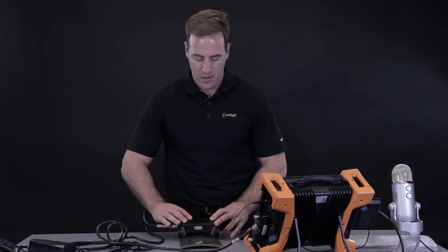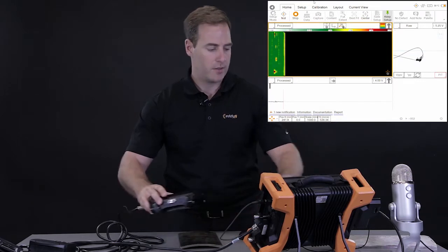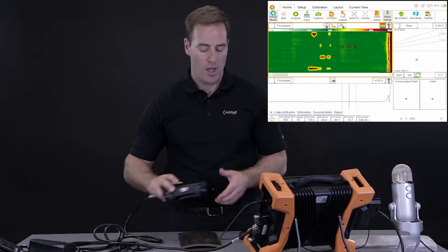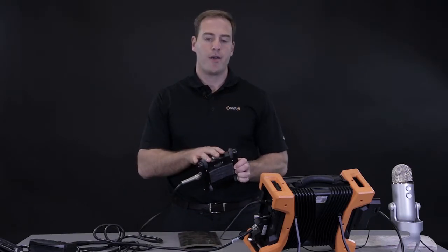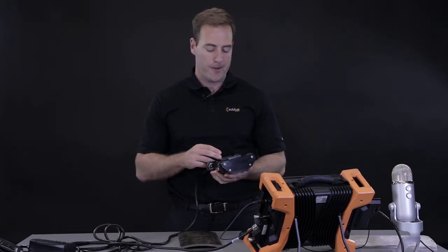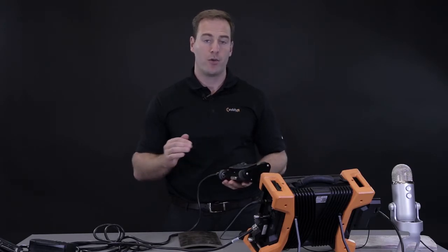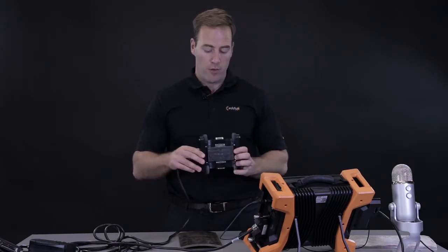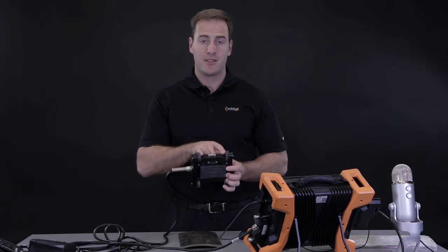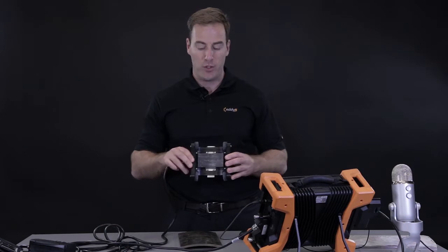I'm going to use the touchscreen of the instrument now, scanning the defect like this. And here we go, stop the acquisition. With this high resolution version of the Sharck probe, we have a smaller element, as I explained before, and we have 3 rows of coil to get a higher resolution. The coverage of this probe is about 75 millimeter, so a bit wider than what we got with the Sharck probe.